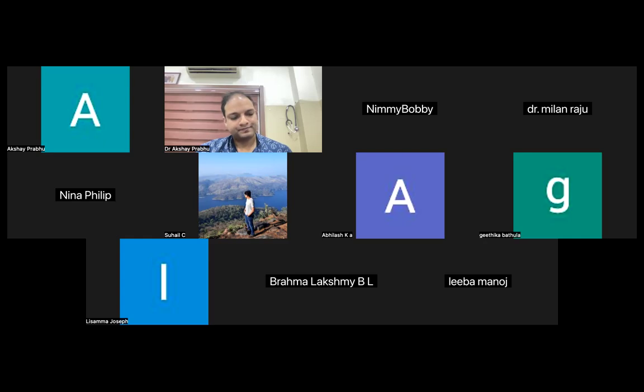Correct. So if we are using minimum and coagulating and cutting, it just takes longer. And that would be done at the 3. If you're keeping it at 3 and 5, that would be done at 3. The coagulation and cutting happens at 3. While if you are using the maximum button, the coagulation and cutting is happening at 5. But it is faster. The coagulation or the thermal energy is less, and it gets cut faster. Absolutely. I understood that the pressure used can be different and the cutting can be different with different pressures, but with the same pressure used, when we're using the minimum button, it works at 3, and when we're using the maximum button, it works at 5.